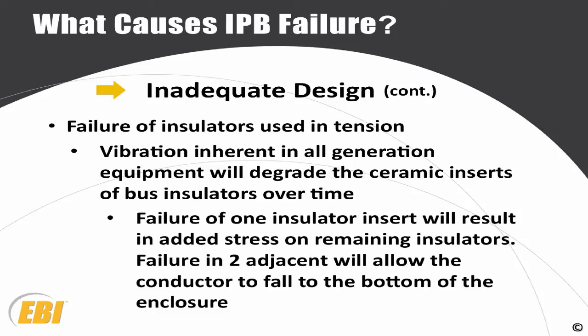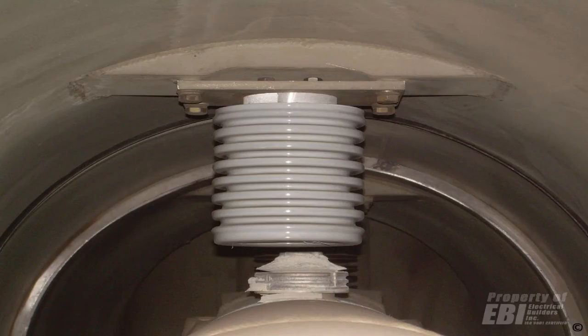Under normal situations, that's really not a problem, but this bus vibrates. Anything you hear hum in a power plant, you have vibration. And after about 20 years of vibrating, this is what happens. The ceramic inserts inside the insulator will actually come apart. Normally you have two insulators per section of bus, and then you have laminated flexes that attach the conductor to the next section of bus. So if you lose two on the same section of bus, the conductor falls down into the bottom of the enclosure, and you have a rather large failure at this point.